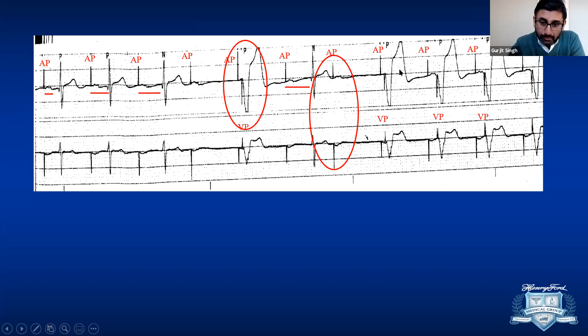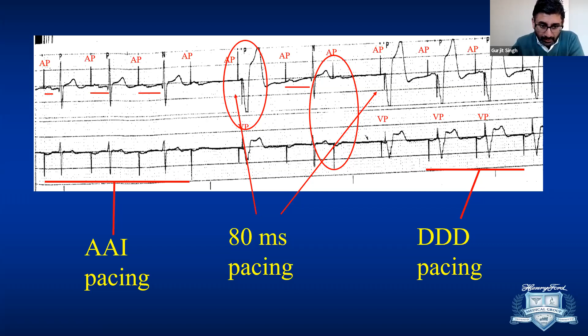You see 2 out of 4 atrial complexes losing conduction, and the pacemaker switching to DDD mode. Okay, so this is MVP in action. Again, briefly, MVP is AAI pacing, AAI mode in the atrium. The moment you lose conduction, 2 out of 4 beats, you switch to DDD, you wait for a minute, and then you go back to the same AAI mode. This is to prevent and minimize RV pacing. Okay, next slide. Noise, noise, noise.